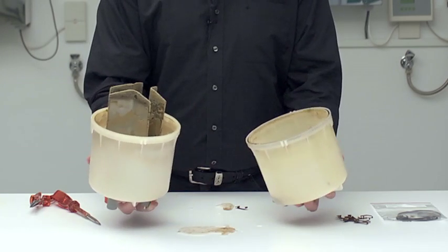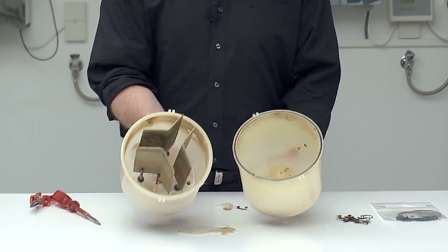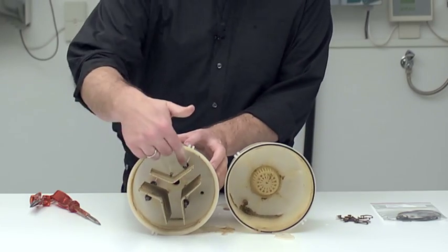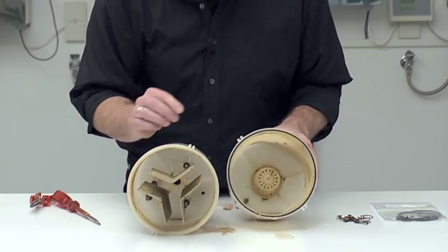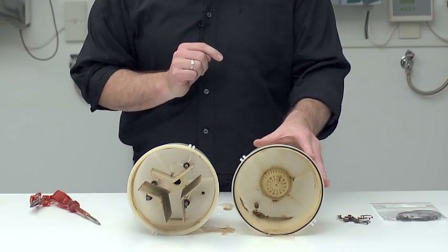Well, you can see a little water does still come out. Here we have some light mineral deposits on the electrodes and some deposits in the lower part. If you can see a relatively large amount of mineral deposits from the outside, it would be a good moment to take a look.